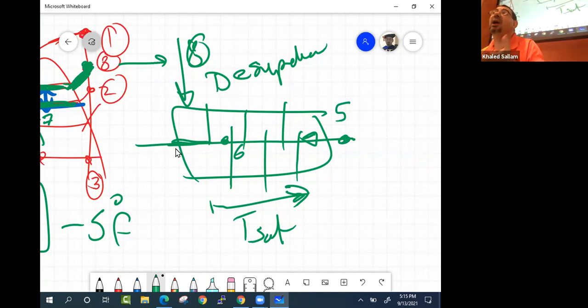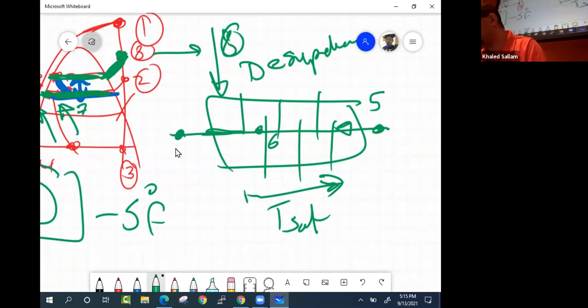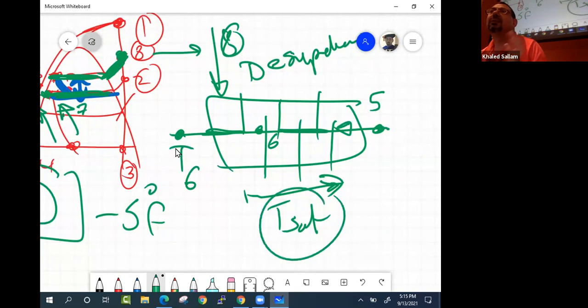So they stuck with the terminal temperature difference definition, which is what is the exit temperature compared to T saturation of the steam. Because of that definition, you look at the chart, and when you look at the big chart of a power plant, you will see TTD numbers.